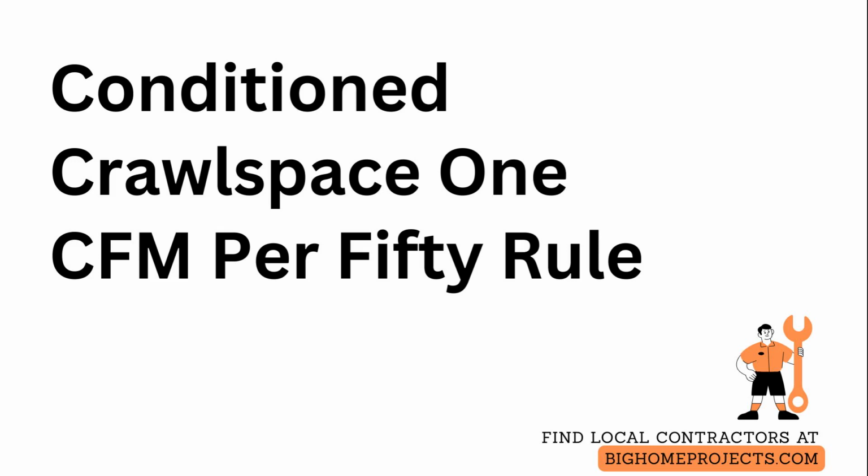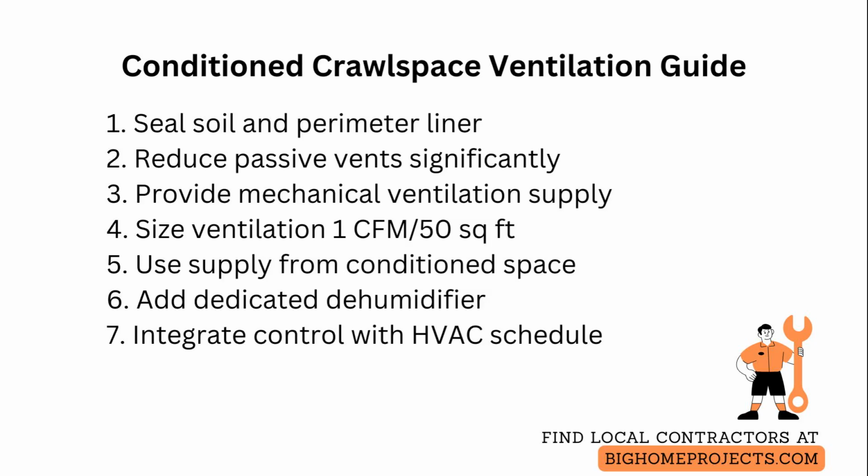When conditioning a crawl space, follow the thumb rule that passive venting must be reduced and mechanical ventilation provided to control moisture and pressure. Conditioned crawl spaces require shifting from traditional passive ventilation to controlled air management so the space stays within the house thermal and humidity envelope.